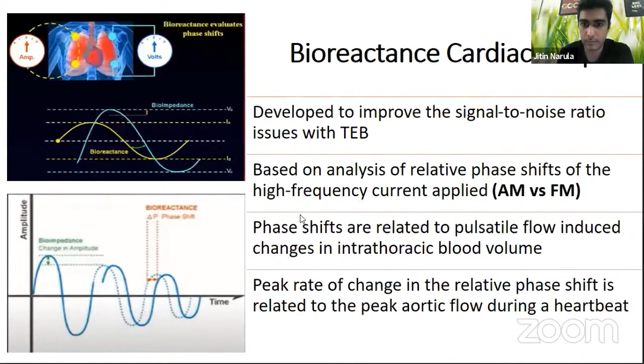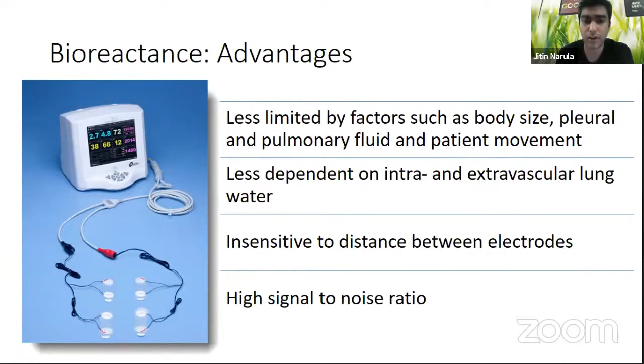So phase shifts are related to the pulsatile flow induced changes in the intrathoracic blood volume, and the peak rate of change in the relative phase shift is related to the peak aortic flow during a heartbeat. So the advantages are that it is less limited by factors such as body size and pulmonary fluid and patient movement, less dependent on intra and extravascular lung water, and it is insensitive to the distance between the electrodes and has a high signal to noise ratio.